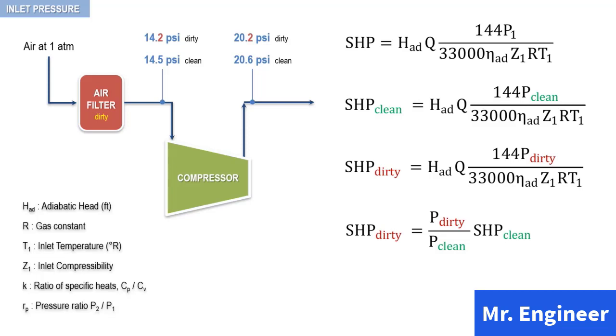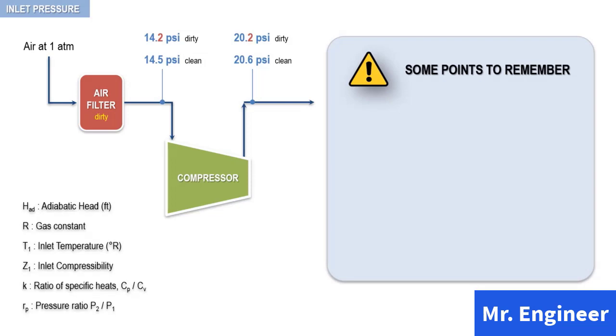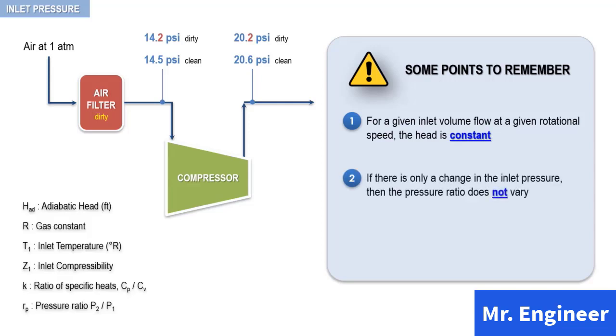Substituting for P dirty and P clean, we can see that a decrease in inlet pressure will result in a decrease in power requirement. Some points to remember: first, the head produced by an impeller for a given rotational speed and a given inlet flow is a constant. Second, if there is only a change in the inlet pressure, then the pressure ratio does not vary. Finally, keep in mind the useful relationship describing the effects of a variation in inlet pressure on shaft horsepower.